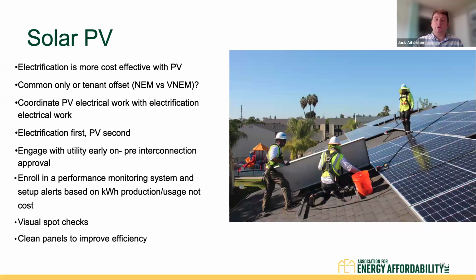Coordinate PV electrical work with electrification electrical work. If you're upgrading your electrical, make sure it's PV friendly, so that when you do your PV scope, you don't have to tear out things that you just installed. We typically recommend electrification first, PV second, so that you can get a better understanding of your new electrical loads in your building. It's predictable, but it's better just to have a baseline of actual usage. Engage with the utility early on for pre-connection approval. Pre-connection can take some time.